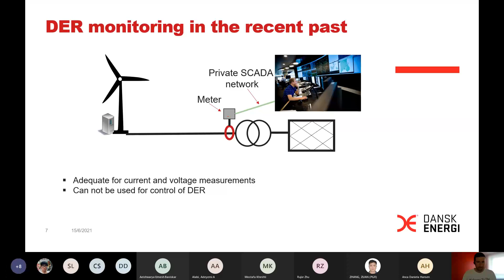That was an adequate snapshot, but there was no possibility for control in any way. It was a one-way connection, and so in terms of optimizing network capacity, the absence of control is not optimal. You can't control the voltage or change set point values for these local controllers, and there is no feasibility for any sort of closed loop or low latency type of control.